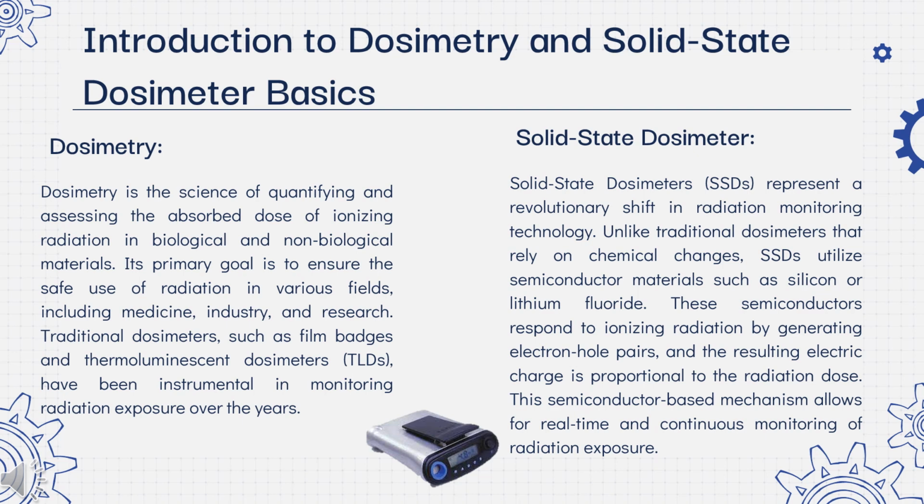Now we're talking about the solid state dosimeter. The solid state dosimeter is presented as a revolutionary shift in radiation monitoring technology, as the traditional dosimeters rely on chemical change. The solid state dosimeter uses semiconductor material, like silicon or lithium fluoride. This semiconductor responds to the ionizing radiation.